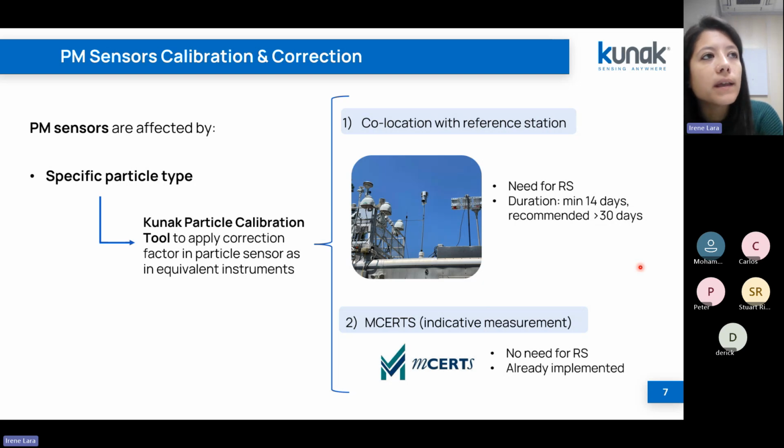Yeah, so the way the sensor works is similar to equivalent instruments. I don't know if you are familiar with these equivalent instruments. Which one? Palas, this kind of, so they use a factor depending on the particle. The thing is that in order to determine that factor, you will need to use the reference method, which is the gravimetric method.